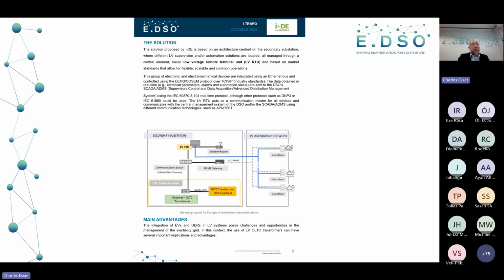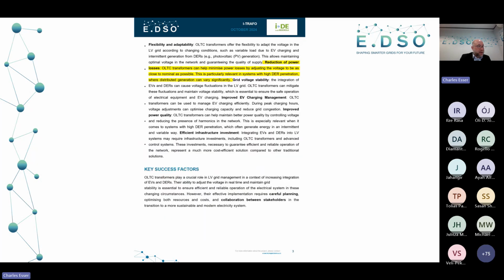One of the things this is able to do, amongst other things, is reduce power losses. These OLTC transformers can help minimize power losses by adjusting the voltage to be as close to nominal as possible. As I mentioned, this is really relevant in high DER penetration, which is more and more the case, particularly in Spain. That's one example.